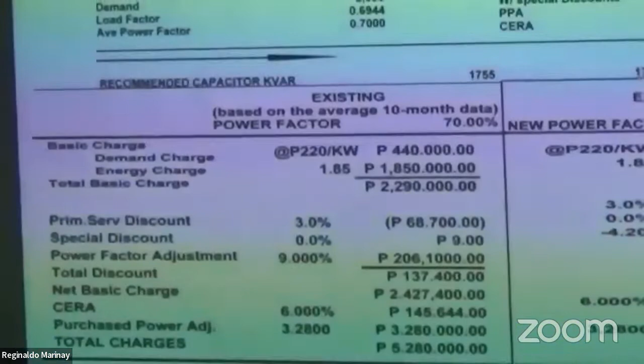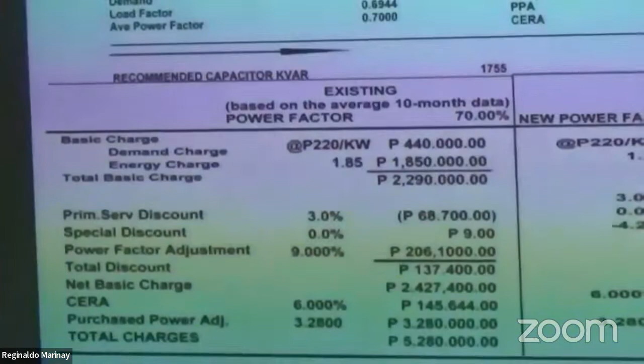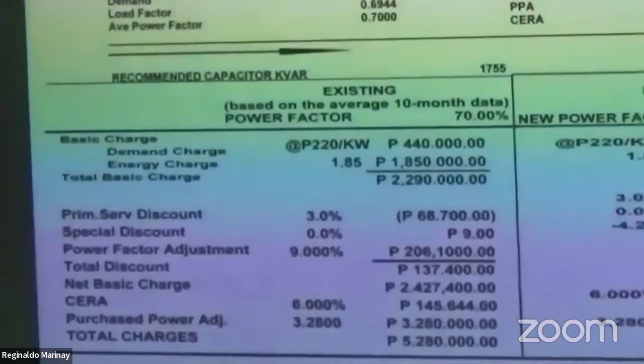Let's go over with the power factor adjustment. Okay? 9%. Where did I get this 9%? Where did it come from? So it came from the 70% minus the 85. You remember, if we have a penalty, how many percent? Penalty, 0.6. Okay, that is 70, right? So we have 85 minus 70%, and that is how much, guys? 15%. And then multiplied by 0.6%. So just forget about the percent here. And that will give us 9. Actually 9%. Let's go back to return the percent. So we have now the 9% here, right? 9% of what? 2.29 million. That's the 9%.